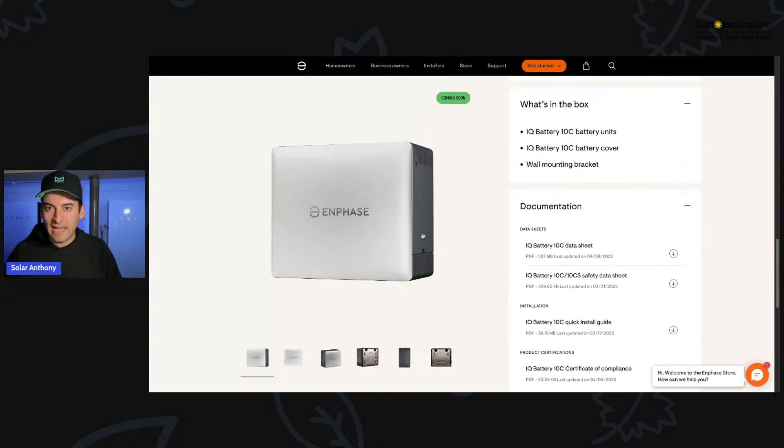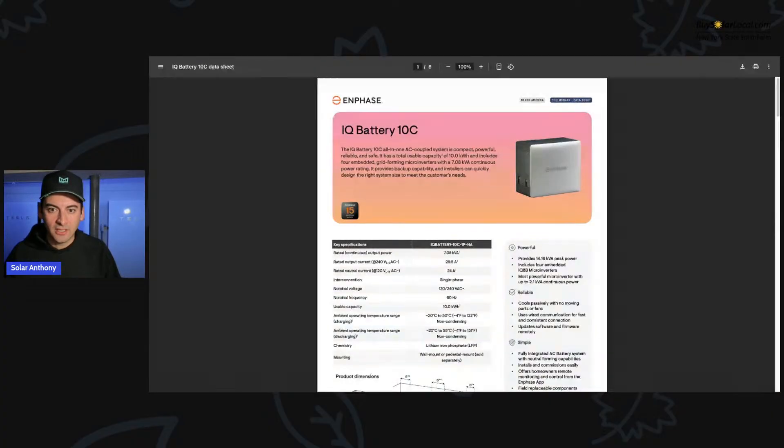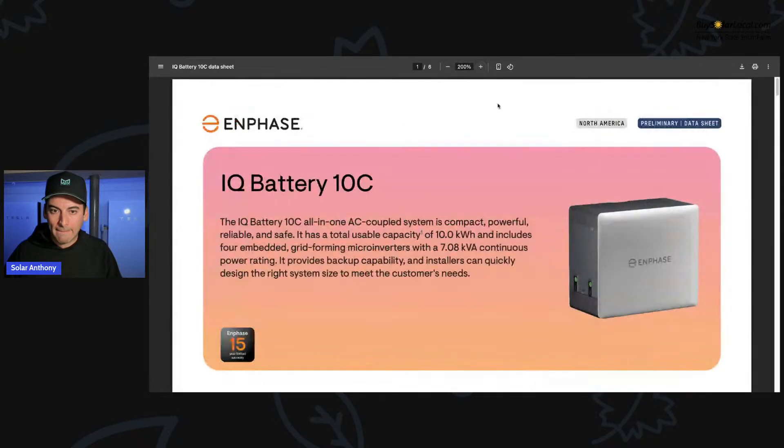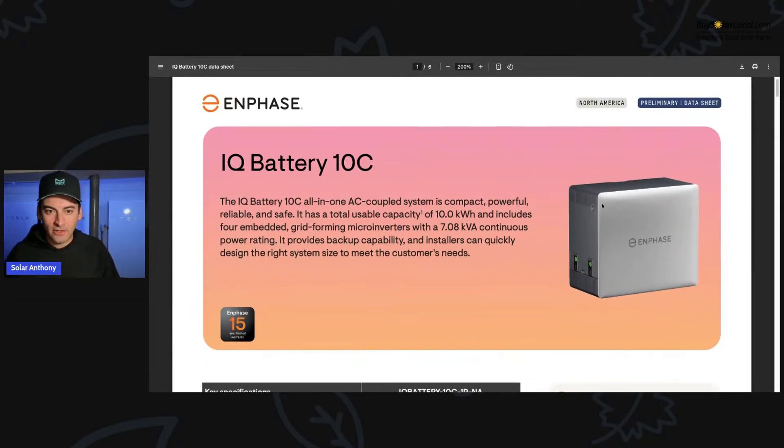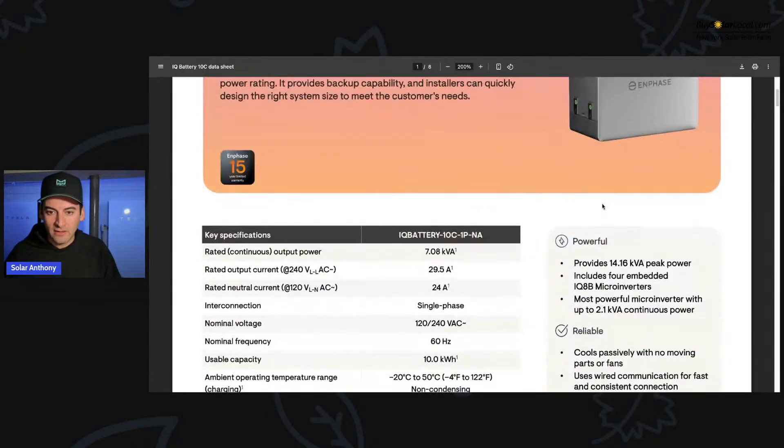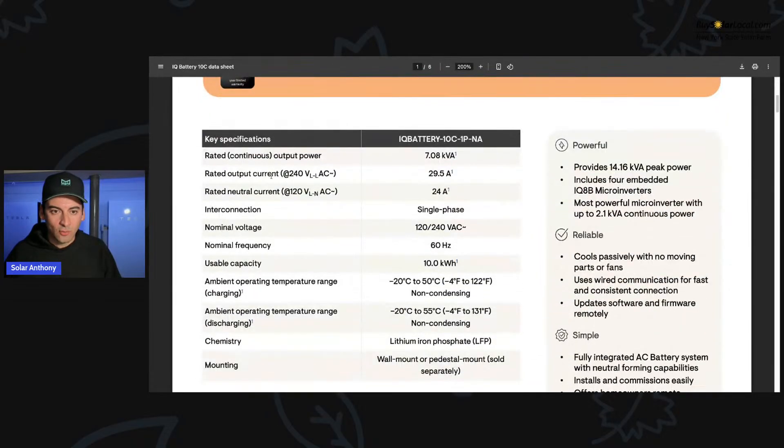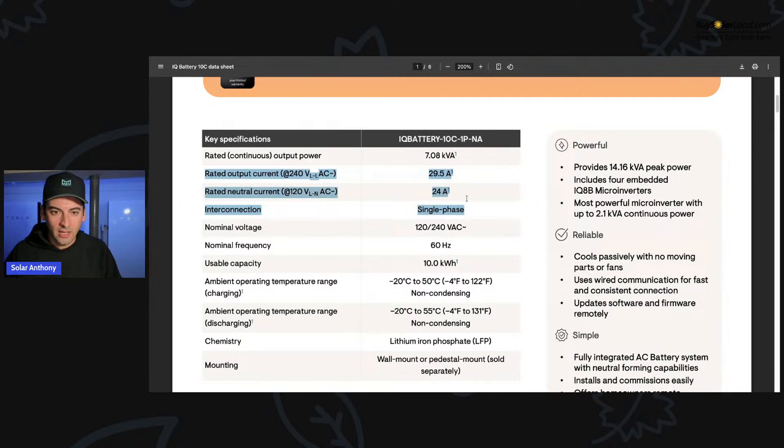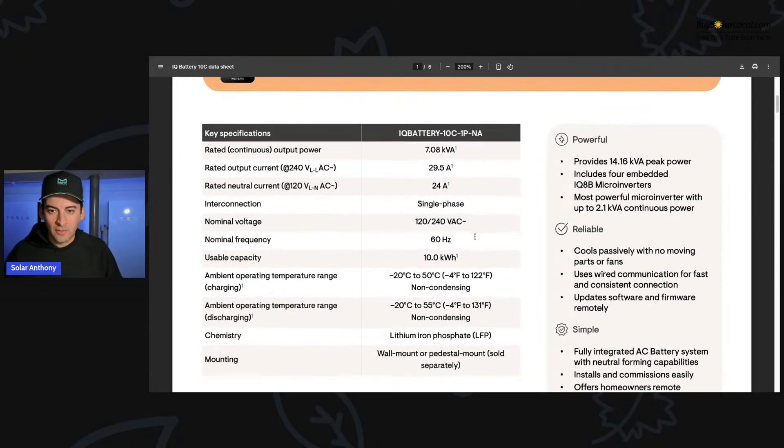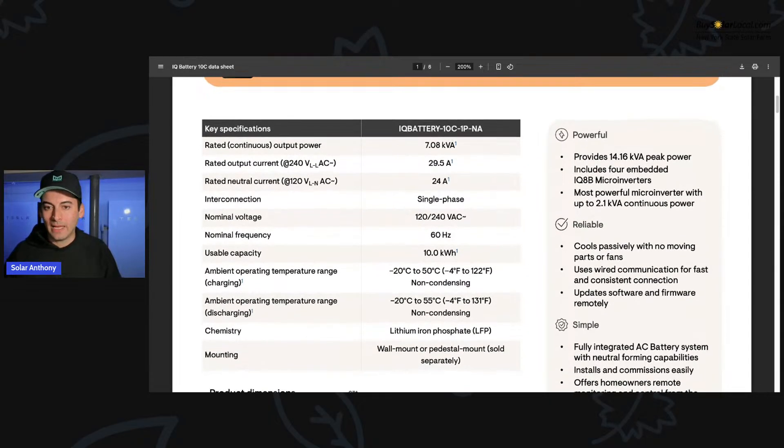So here's the data sheet. Let's jump into that data sheet and see what we have here. So let me blow this up a little bit. So IQ battery 10 C. What do we have going on? So rated output current 29.5 amps. You could see right here on the data sheet, interconnection, single phase, all of these batteries are single phase. Nominal Hertz, usable capacity, 10 kilowatt hours of usable capacity.